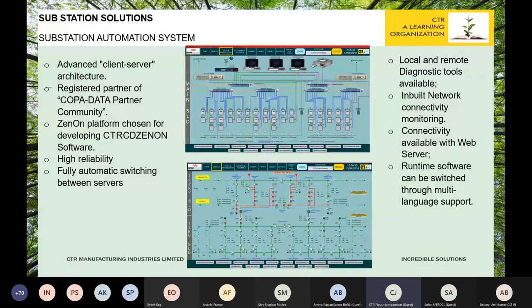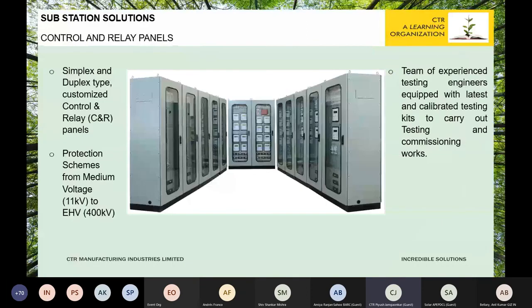Then we have the C&R panels, or control and relay panels. These C&R panels are designed as per the utility specifications or the end customer requirements. They are available in simplex and duplex type customized panels. The protection schemes are designed for medium voltages from 11 kV to extra high voltages up to 400 kV as per the specifications. The testing and commissioning works are carried out by experienced testing engineers using calibrated testing kits.